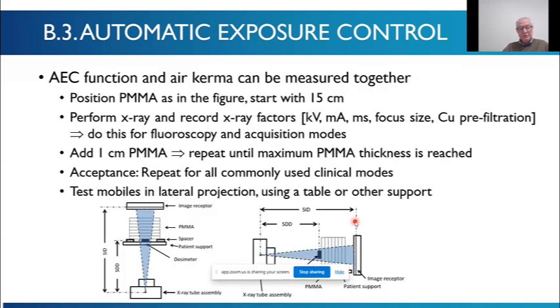Okay, and to do the measurement, you position your PMMA, for example, on the table. Start with 15 centimeters for, like, adult programs, do some X-ray, like fluoroscopy, and record your factors. The actual factors you can record may vary. Some systems may not show all of this information immediately. You may have to go to the SR report to find it. It can be quite hard to find on some units. Some systems it's clear, but you need to record these factors and then keep adding PMMA until you get to the maximum PMMA thickness, which could be 35 or 40 centimeters, depending on how much PMMA you have.